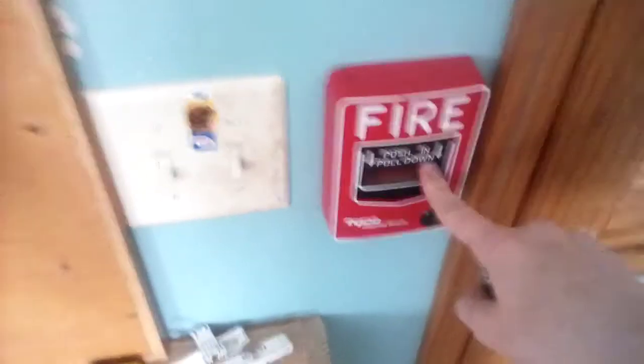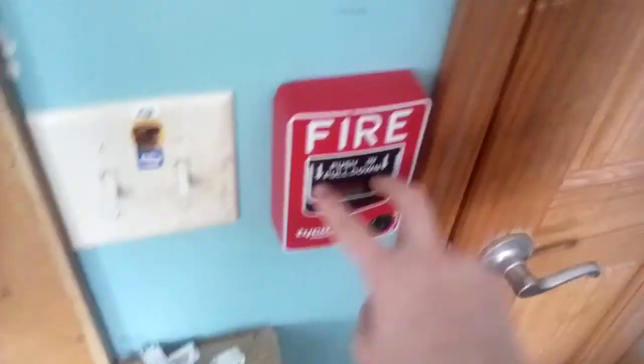The panel is coding that to temporal. Entryway pull station. So while that resets — that's reset. Now we're going to pull the Tyco TIS BG12L.